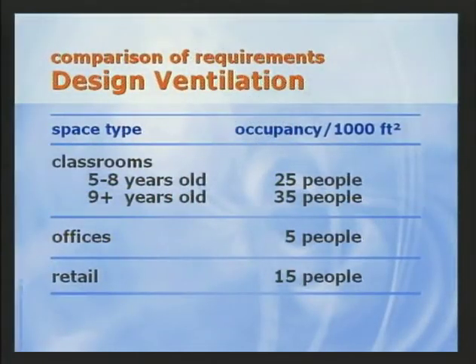From the perspective of design heating and cooling load, classrooms differ from other types of spaces with regard to the number of people that typically occupy a space. Just as we learned, ASHRAE Standard 62, Addenda 62N, assumes that typical occupant density is 25 to 35 students per 1,000 square feet. To put this into perspective, Standard 62 assumes 5 people per 1,000 square feet in offices and 15 for retail spaces. With the amount of outdoor air required in a space driven heavily by the number of people in the space, classrooms typically require 45 to 50% of their supply air to be outdoor air.